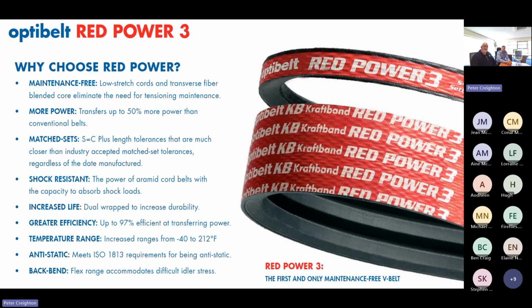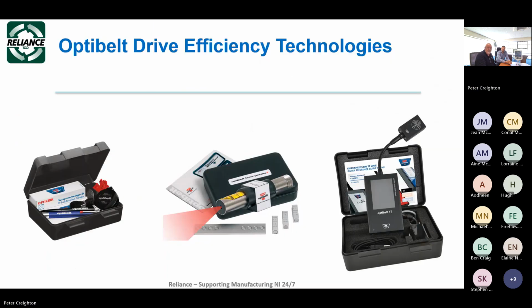The Red Power belts are set up exactly as here, and I don't need to go through it too much. It meets all the ISO requirements. It'll run over a very good temperature range from minus 40 degrees to 212 degrees, and it can transmit up to 97% efficiency. Setting up is very important. There are kits that you can buy off us, or kits that you can buy off anybody else. So it's not just Reliance, but we would recommend that you set them up properly, with correct alignment and correct tensioning.